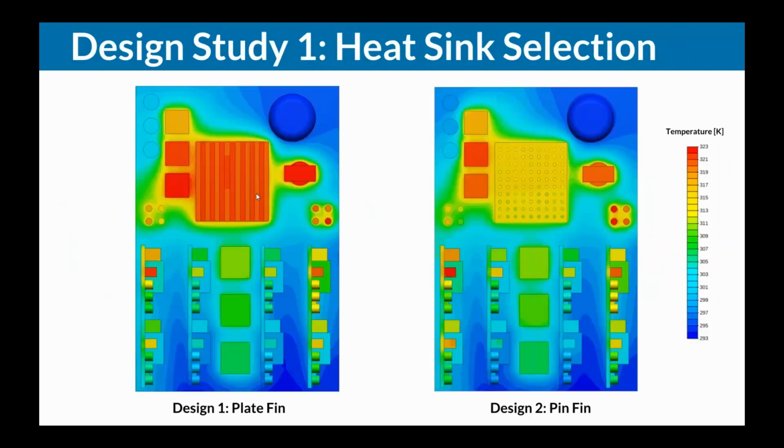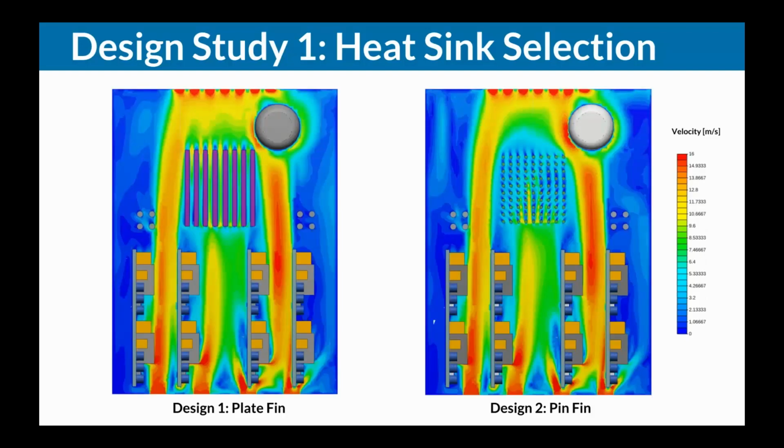Confirming that with the top view. And I think the important piece is all the other components, as we would expect, are not really affected. We can see that the flow field might be affected around the pin fin heatsink to also have an effect on the components around it. But overall, the massive impact is on the CPU.